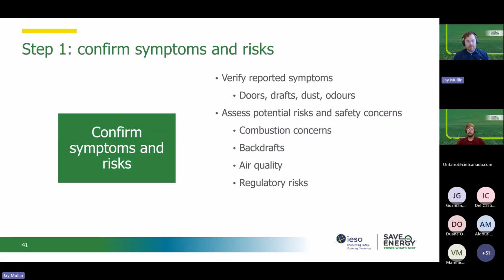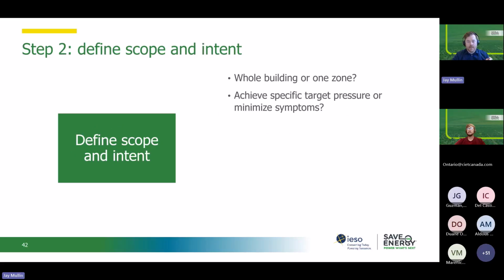So, if you're starting to see some symptoms of negative or positive pressure, you want to assess if there are any safety concerns. So, combustion concerns: could there be a risk of combustion products not being fully exhausted? Is there a potential for backdrafts? Are there air quality issues? Are there regulatory issues? Do you need to maintain certain pressure differentials, and could that be put at risk? If it's just that we think we can save energy, that's a great benefit, but it's not necessarily a risk. Where if there are actual health or regulatory risks, that can make it a really big priority. So it's important to understand that and check that.